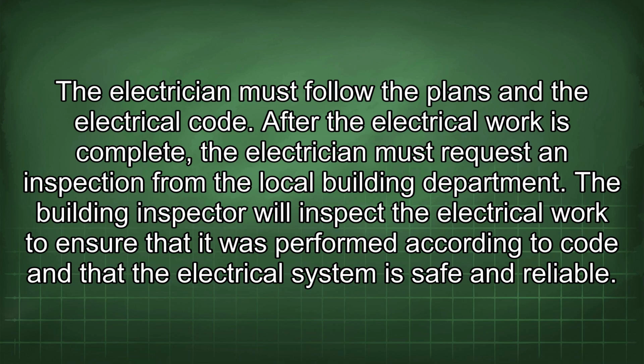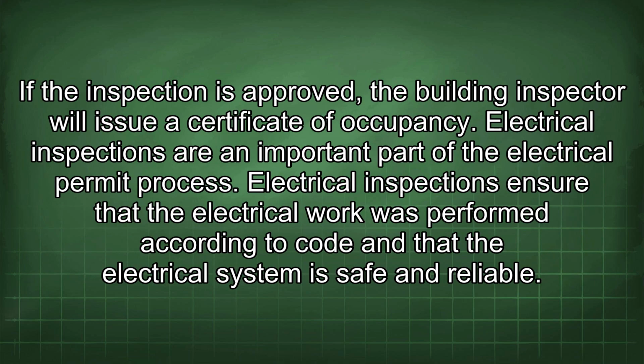After the electrical work is complete, the electrician must request an inspection from the local building department. The building inspector will inspect the electrical work to ensure that it was performed according to code and that the electrical system is safe and reliable. If the inspection is approved, the building inspector will issue a certificate of occupancy.